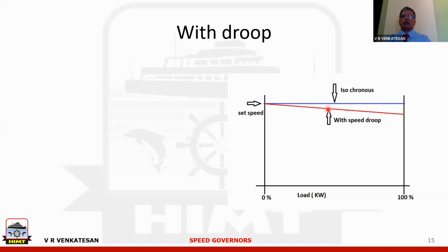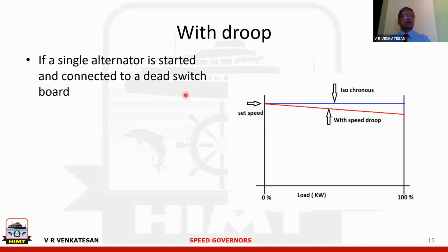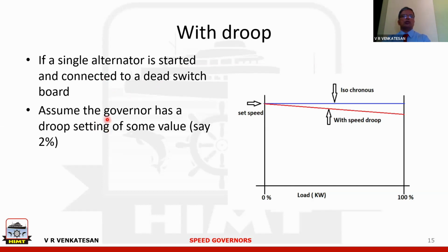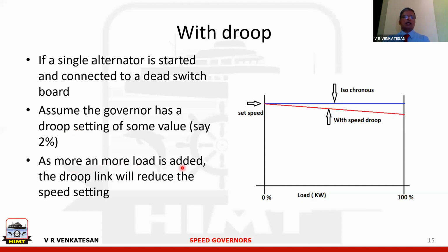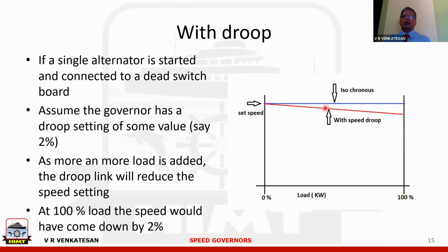And the meaning of 2% droop setting is, if you keep on increasing, it will keep going down. You can see it in this example. So once again, we start the same way. Start with the single alternator. It is started and connected to a dead switchboard. Now assume that the governor has got a droop setting of, let us say, 2%. Then as more and more load is added, the droop link will reduce the speed setting. Since this droop speed setting is reduced, the actual speed of the engine will come down. And the meaning of 2% is, at 100% load, the speed would have come down by 2%. It will be here.